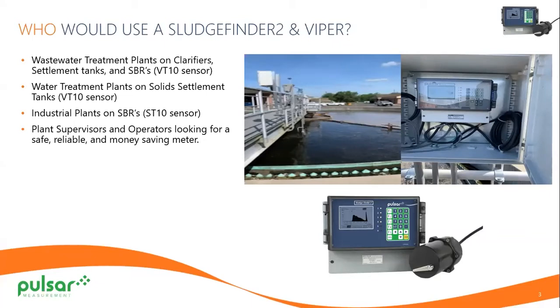Common applications for the SF2, Sludge Finder 2, and Viper are clarifiers and wastewater treatment plants. Most recent example of this for me is in Florence, New Jersey, wastewater treatment plant. They have 2 clarifiers that are next to each other. We installed the Sludge Finder 2 controller on the bridge on the one clarifier and ran the wiring to the second with the Viper sensor into the second clarifier. So now you're able to read both clarifiers in the one controller in the cabinet.